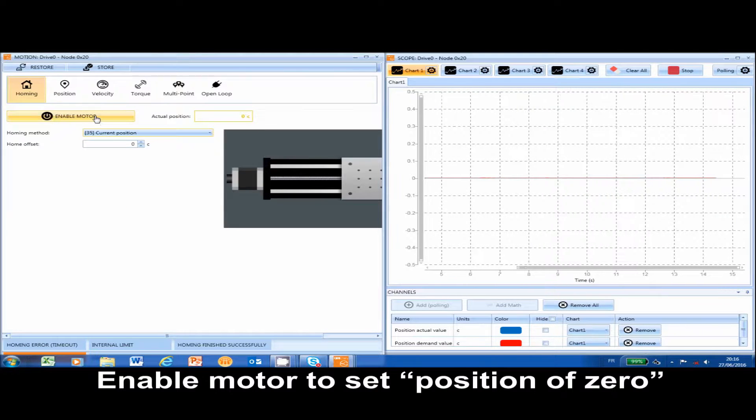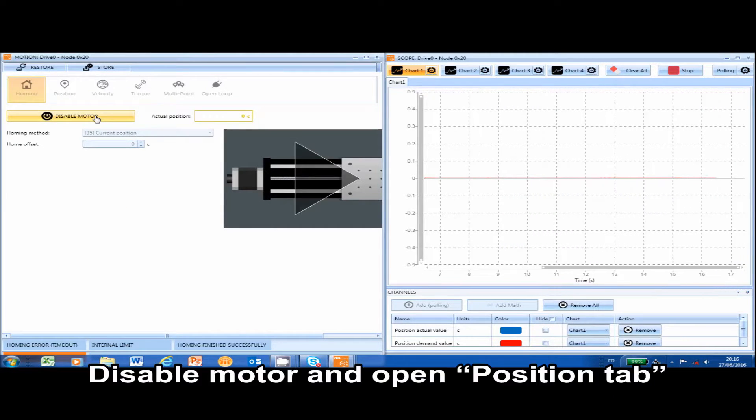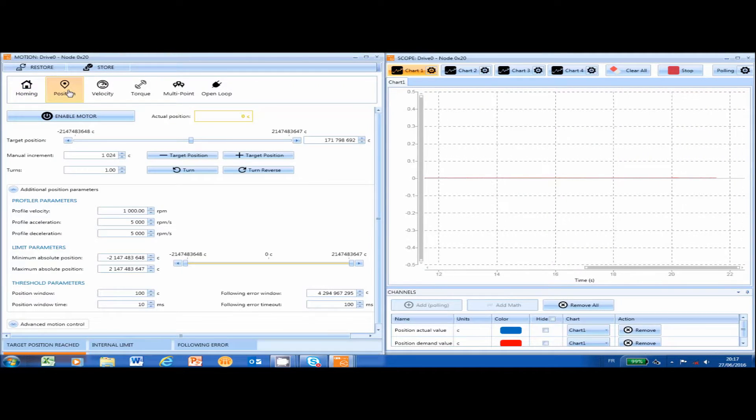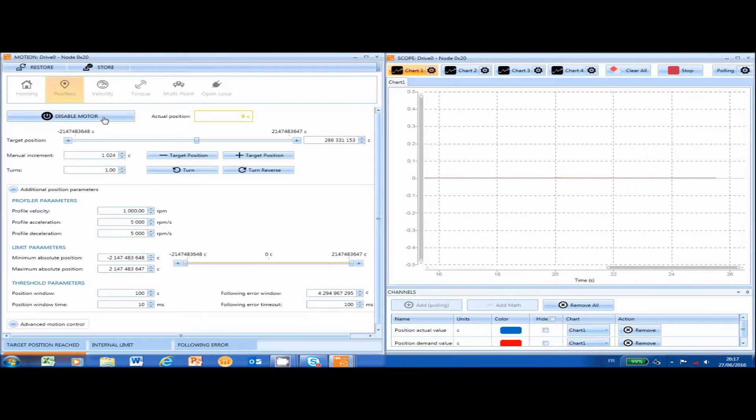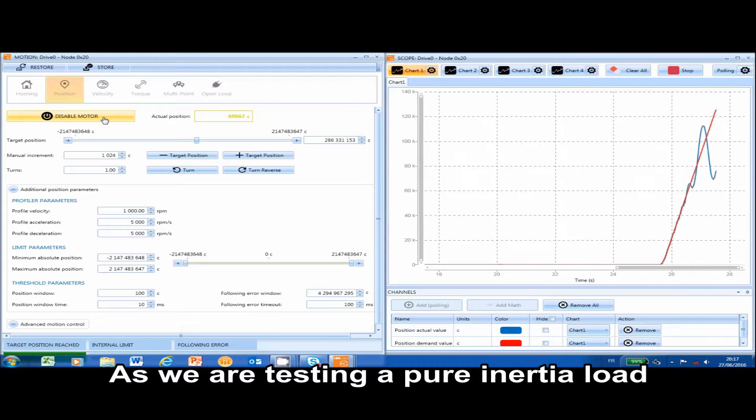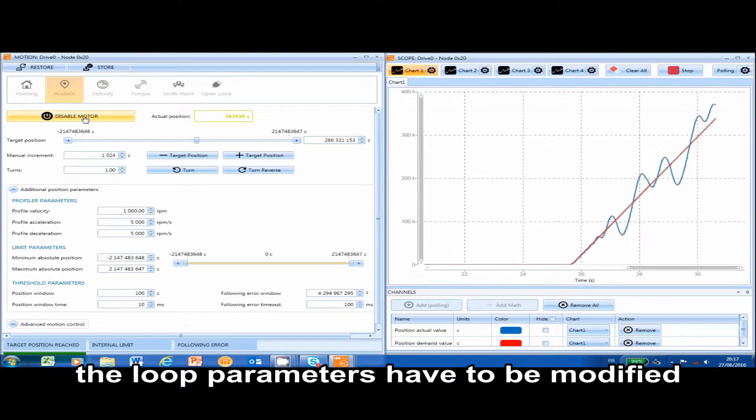Enable the motor to set the position to 0, then disable the motor and open the position tab. Set a position to target and enable the motor. As we are testing a pure inertia load, the loop parameters have to be modified.